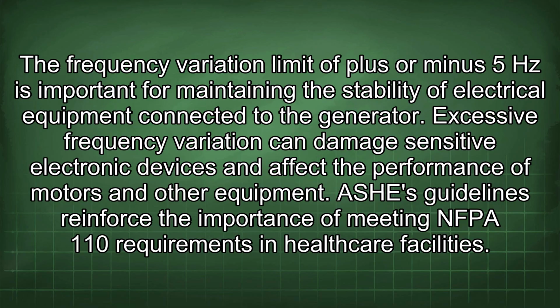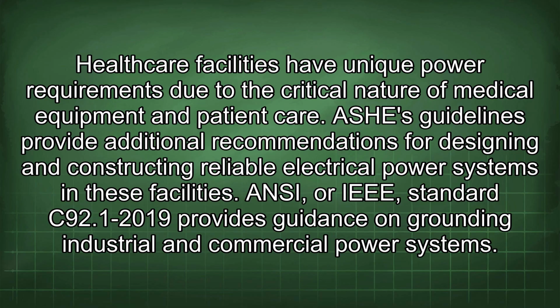The frequency variation limit of plus or minus 5 Hz is important for maintaining the stability of electrical equipment connected to the generator. Excessive frequency variation can damage sensitive electronic devices and affect the performance of motors and other equipment. ASHE guidelines reinforce the importance of meeting NFPA 110 requirements in healthcare facilities. Healthcare facilities have unique power requirements due to the critical nature of medical equipment and patient care. ASHE guidelines provide additional recommendations for designing and constructing reliable electrical power systems in these facilities.